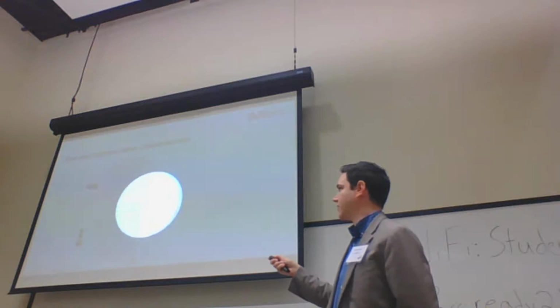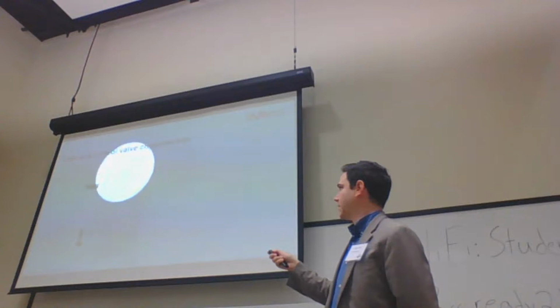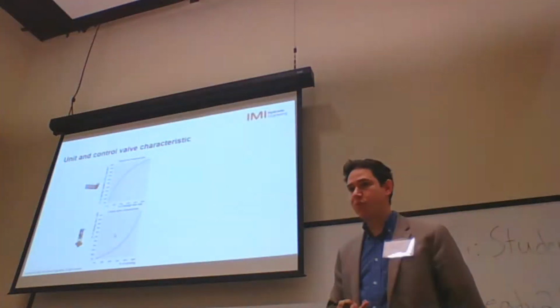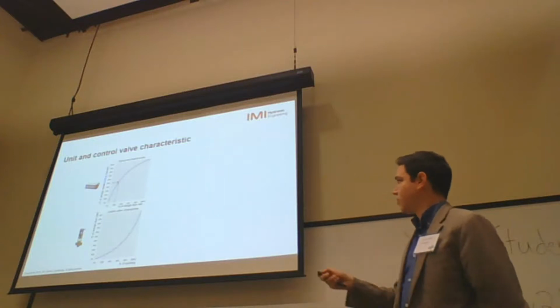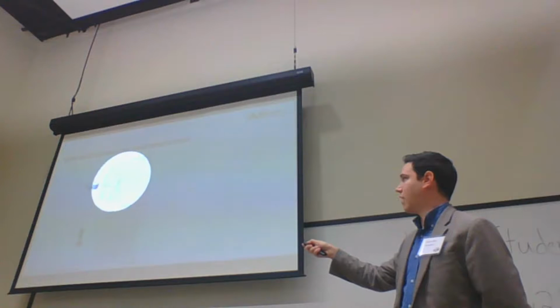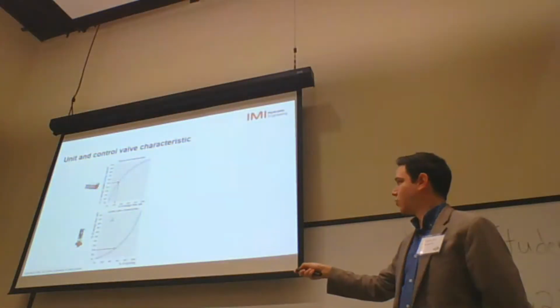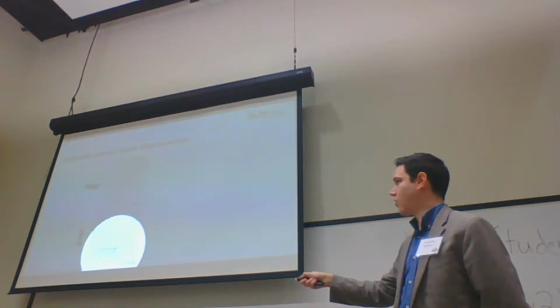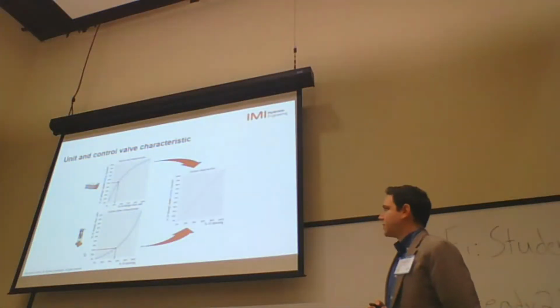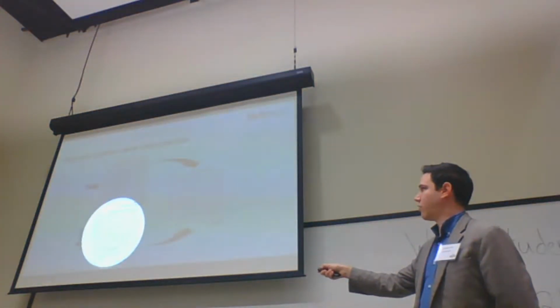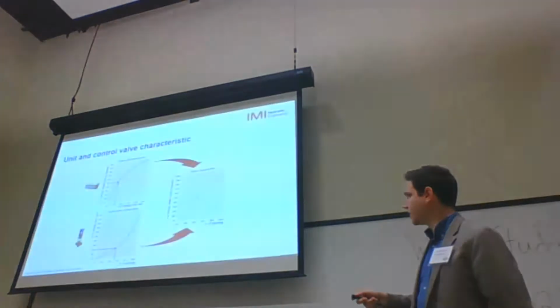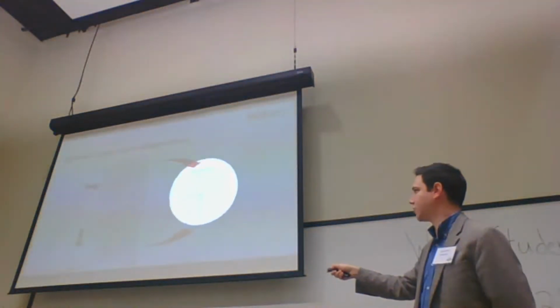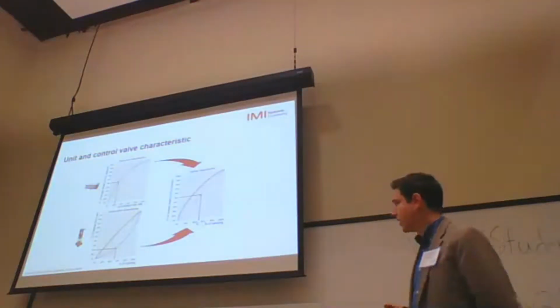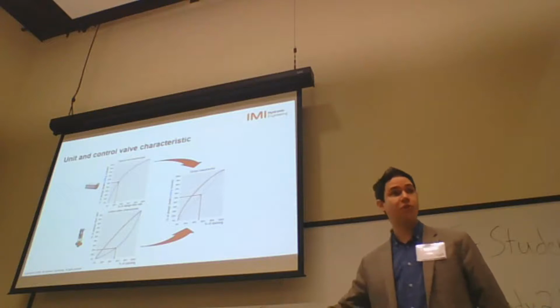Here on the top right we have my coil, the heat output, and the flow rate. My control valve is normally exactly the opposite curve from my coil. It's what we call the equal percentage control valve curve. If I need 50% of the capacity in my coil, I only need 20% of the flow rate. For 20% of the flow rate in the control valve, you only need 50% of the opening. So when I combine the two curves, the coil with the control valve, I get a global linear. At 50% of my coil capacity, I need to open my control valve by 50%. This is the perfect control valve authority, when you have it above 0.25.